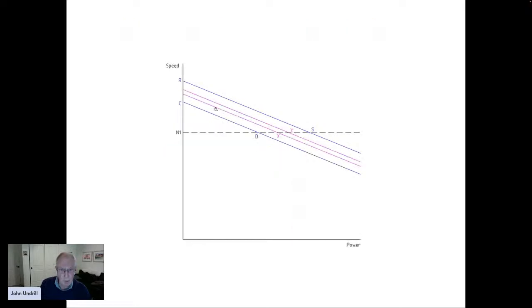If I wanted to redistribute power between two machines, so that I start out with the machines running here and here, and I want to equalize the speeds, then I would have to raise the speed reference setting of this generator from here to here, and lower the other generator from there to there. I'll have effective control of the speed if the power remains constant, or of the power if the speed remains constant.